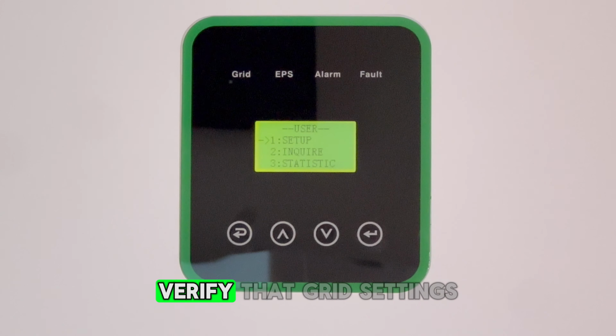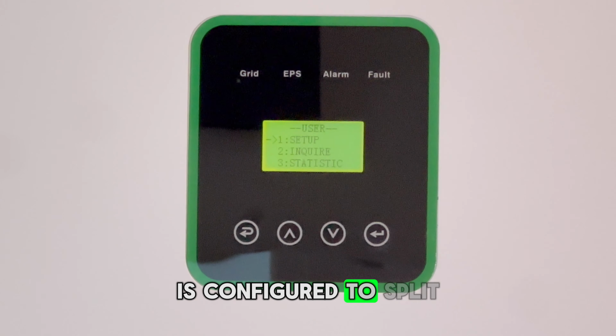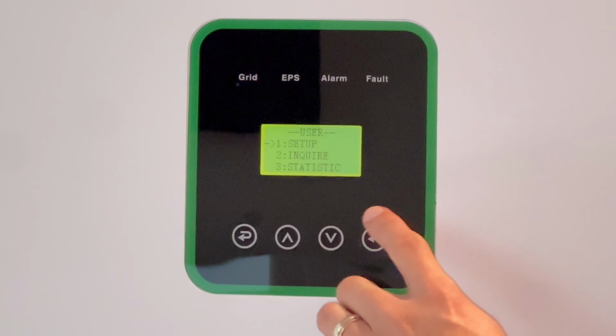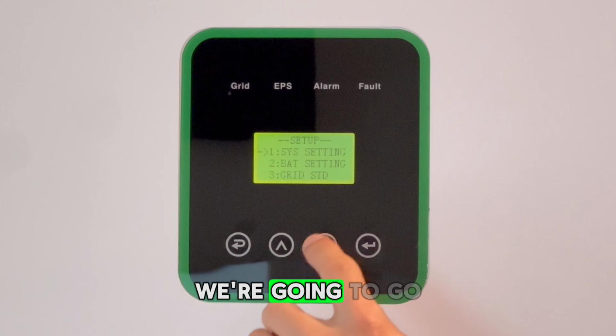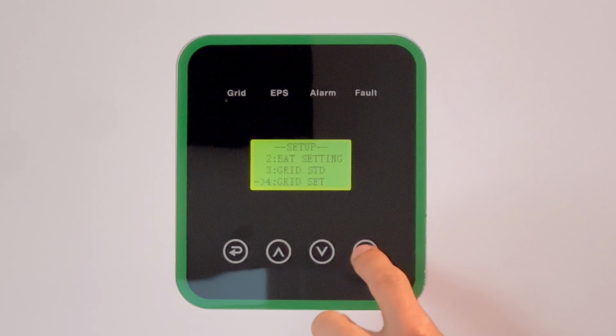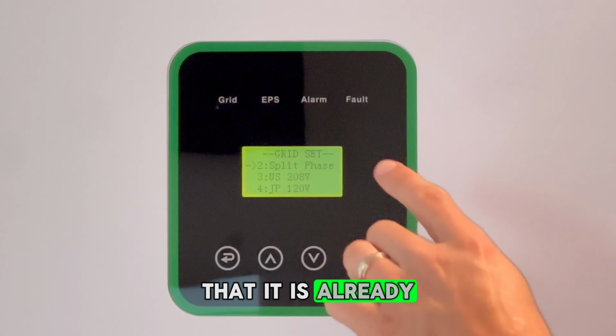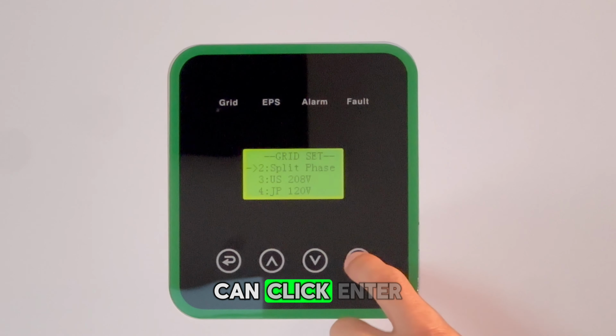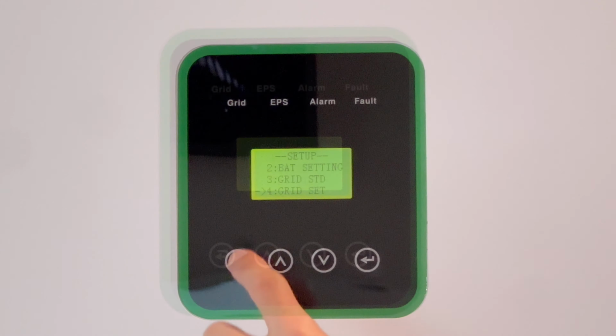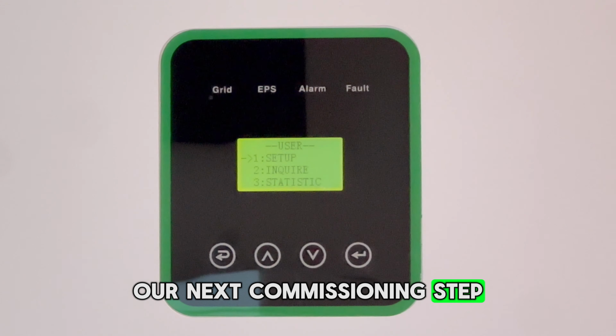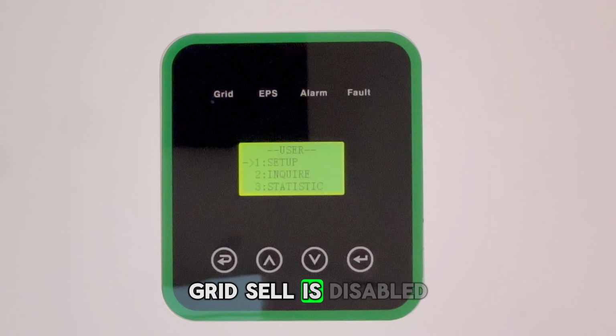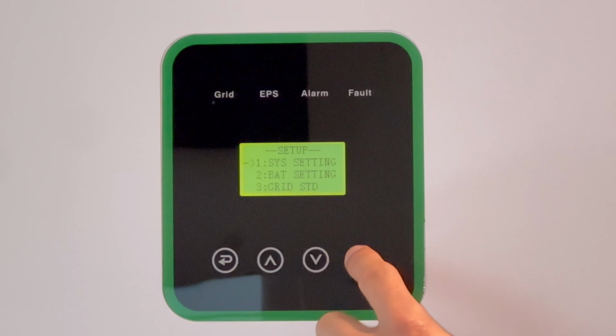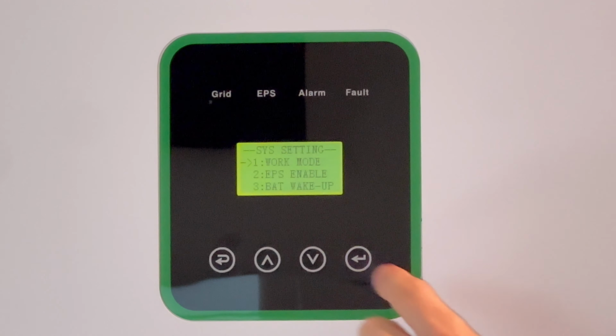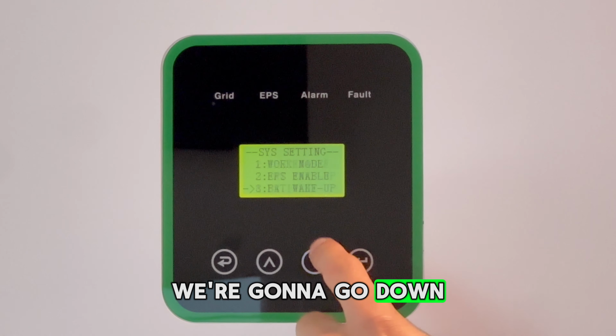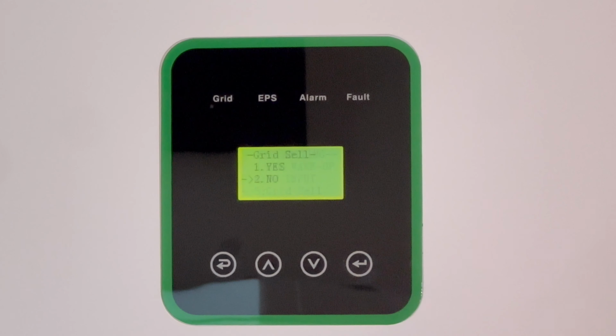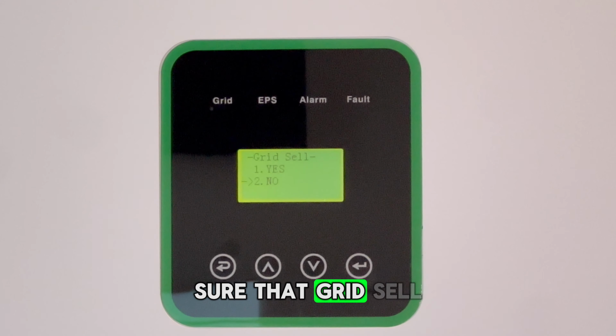Next, we're going to verify that grid settings is configured to split phase. We're going to go down to 4. And we're going to see that it is already set at split phase. We can click enter. Our next commissioning step is that we must verify grid sell is disabled. We're going to go into system settings. We're going to go down to number 5, click enter, and make sure that grid sell is on no.